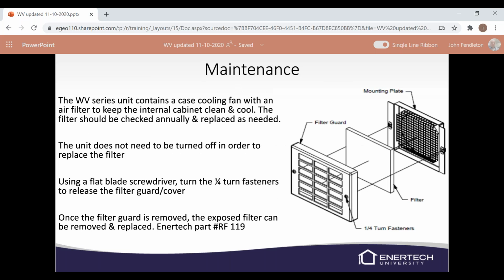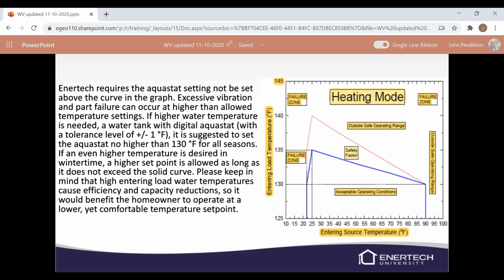Again, this is a case inlet fan. We do have a part, but again, you can just cut a piece of fiberglass filter material and throw in there as well. We do have these heating curves in the manual, and so we require an aquastat setting not be set above the curves in these graphs. What happens when we get out of this operating range is we get a lot of vibration, compressor failures, refrigerant leaks. So make sure we're staying within the safe operating range, which is this blue box here.